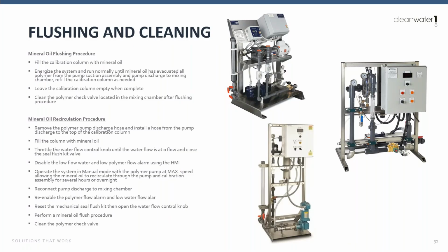There's a bunch of different ways to do this. My recommendation is we can add a flushing cycle, which essentially is a little timer. It keeps the solenoid valve open. So when the polymer system is shut down, the solenoid valve will be set open for a preset amount of time. It allows water to flush through the system, the mixing chamber, and the downstream plumbing. The other consideration, however, is flushing the pump.